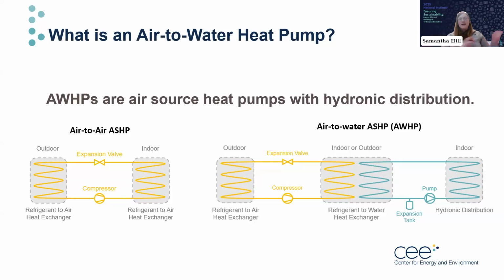And similarly, an air-to-water air source heat pump has those two heat exchangers, but one of the heat exchangers, the one that would usually be providing conditioning to the indoor airspace, instead sends that heat energy into a hydronic loop, a water loop. And then that water can be used in various ways to distribute the energy that the air source heat pump has moved from the outdoor air into the building. And that hydronic distribution can look like radiators, radiant slabs. It can look like domestic hot water heating, lots of form factors. And hydronic distribution systems are really versatile in terms of how they can be set up, and they can be very efficient in terms of how they move heat around a building. And so that's one reason why you'd go to the bother of making an air source heat pump into an air to water heat pump.